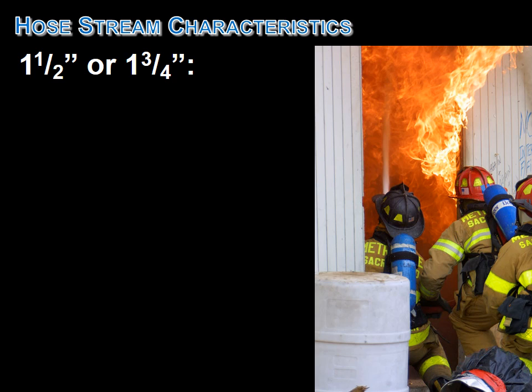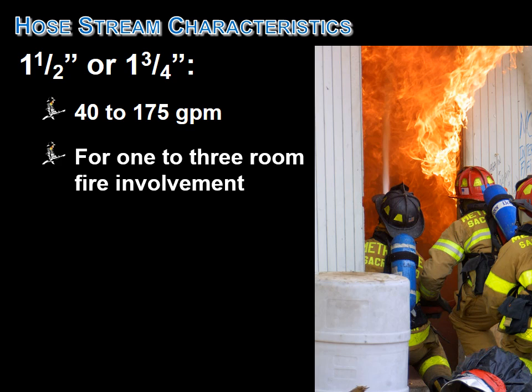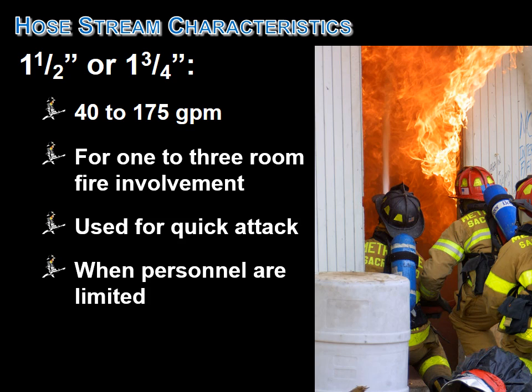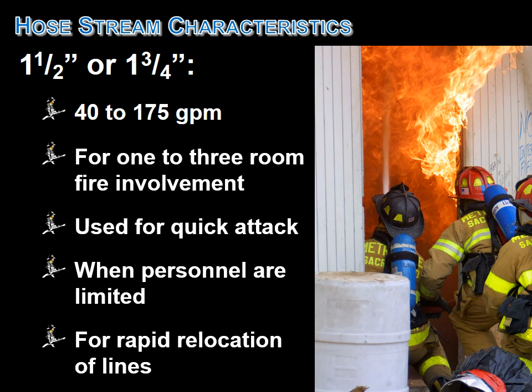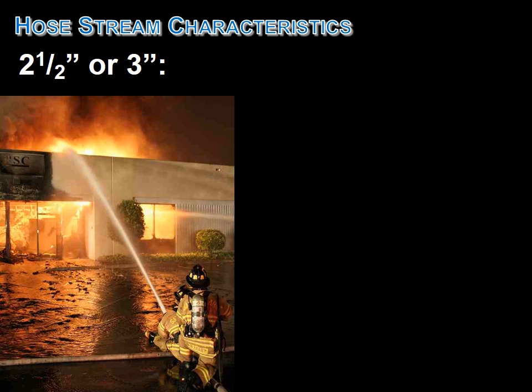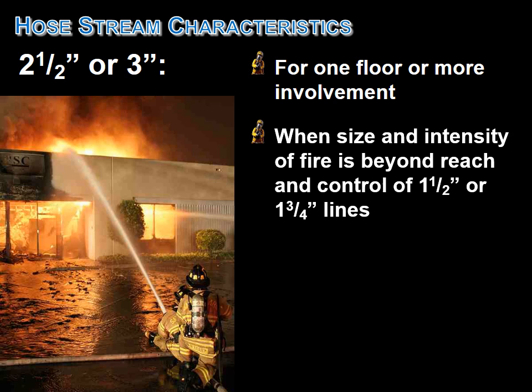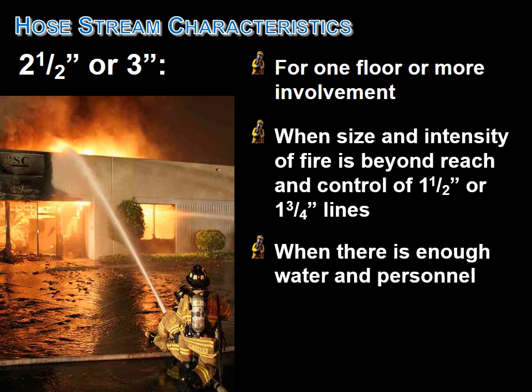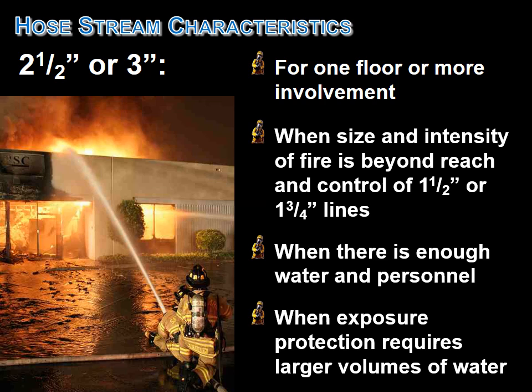Our hose stream characteristics: a 1.5 or 1 3/4 inch hose line, typically between 40 to 175 GPM, for 1 to 3 room fire involvement, used for a quick attack, when personnel are limited, and for rapid relocation of lines. Characteristics of a 2.5 or 3 inch line are for 1 floor or more involvement, when size and intensity of fire is beyond the reach and control of 1.5 inch or 1 3/4 inch lines, when there is enough water and personnel, when exposure protection requires larger volumes of water.